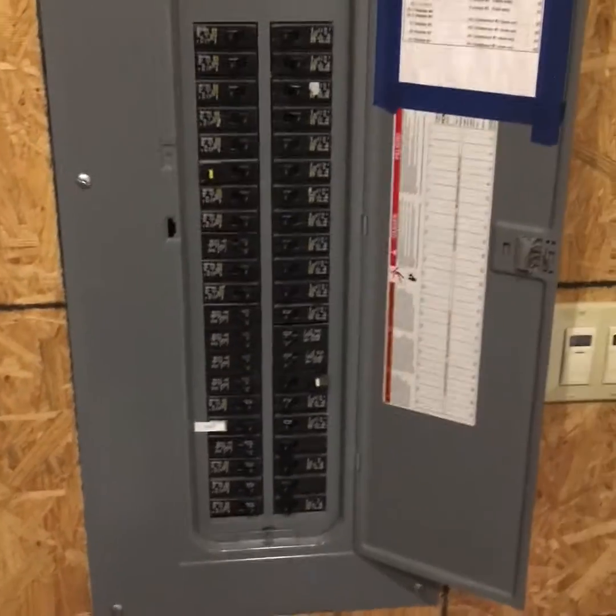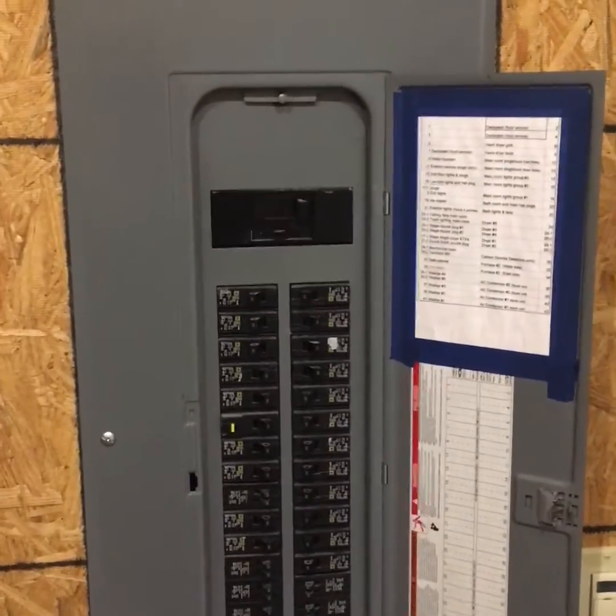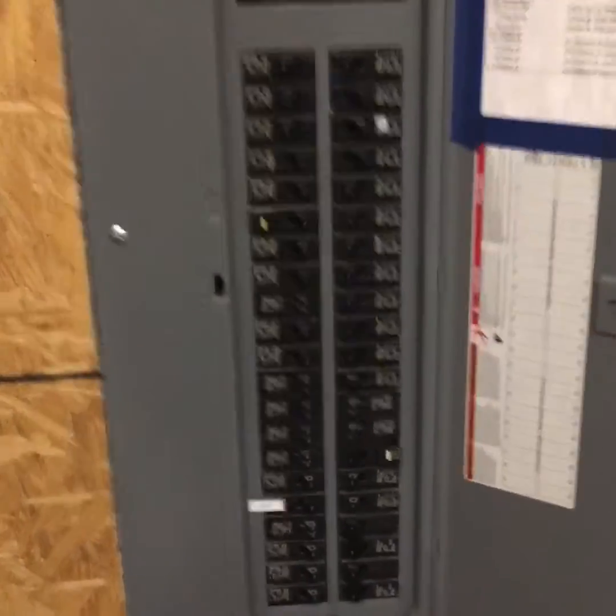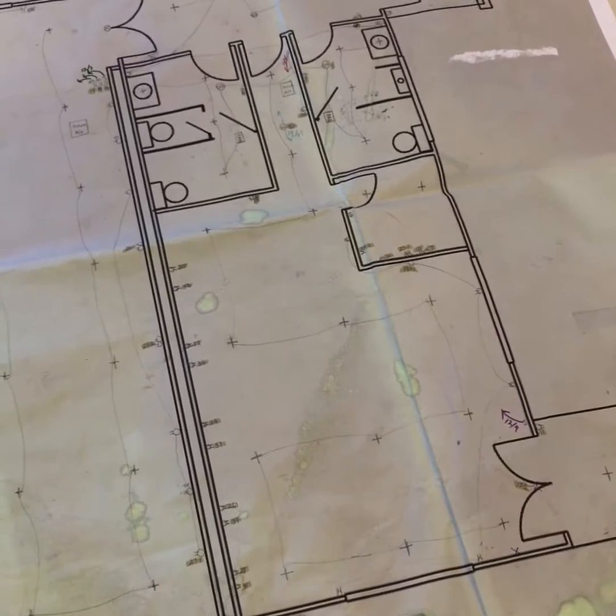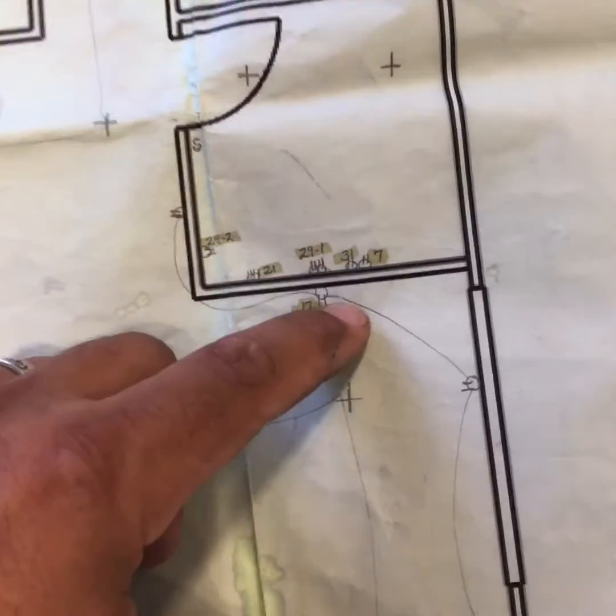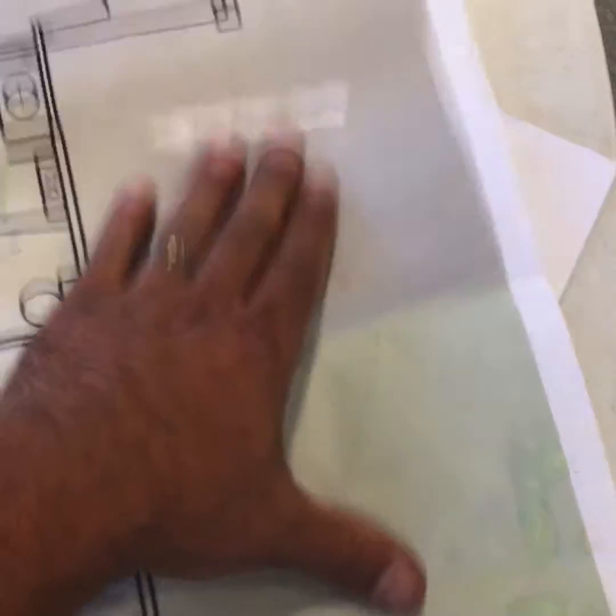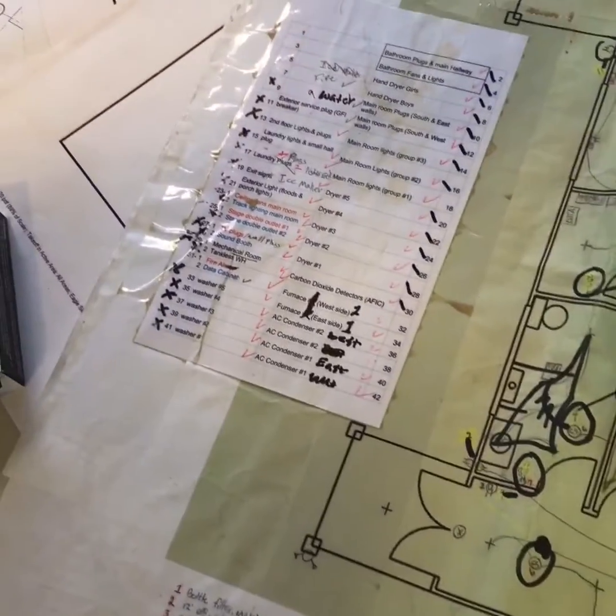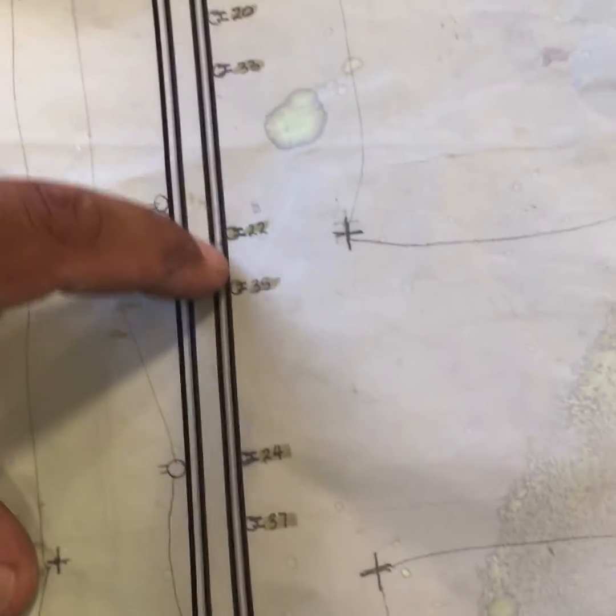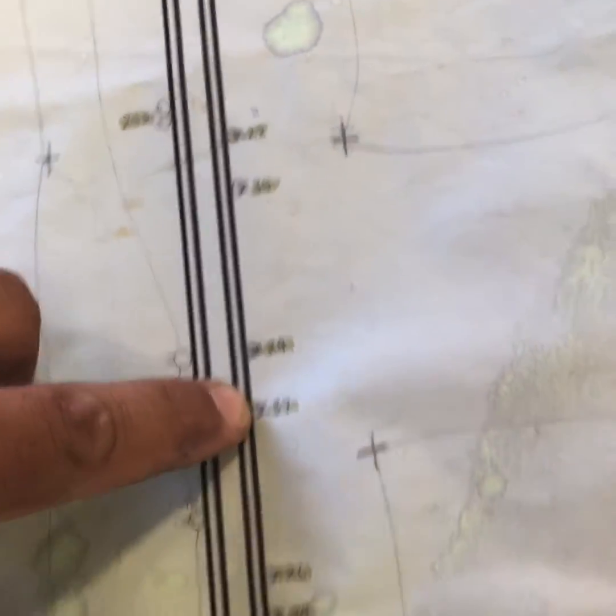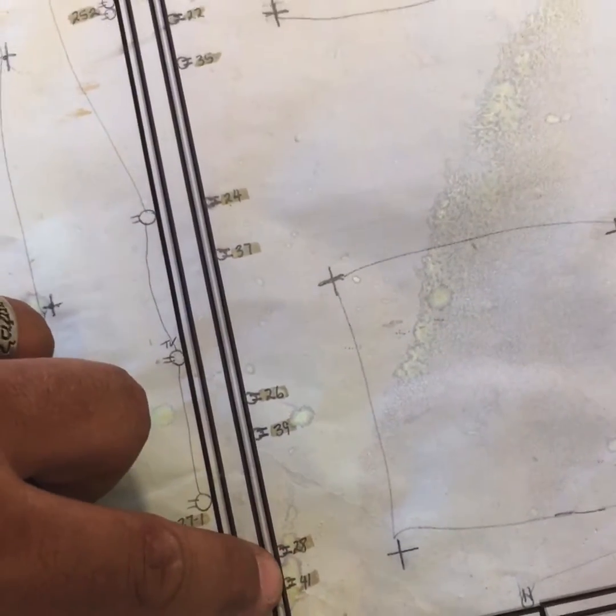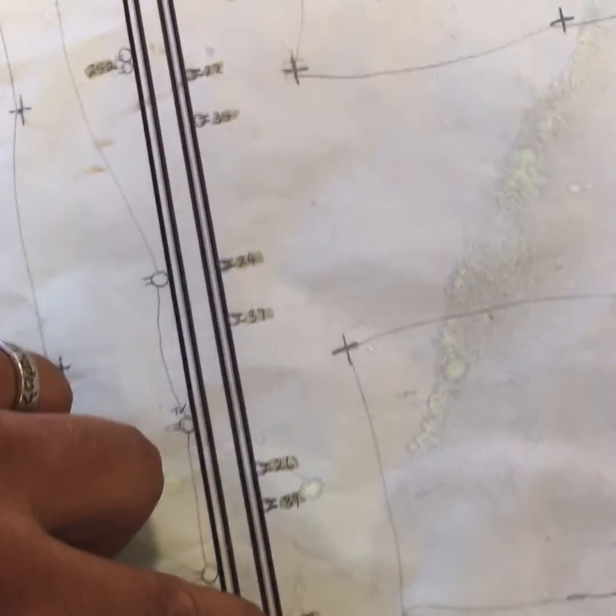And then I think I am going to go up and try to find the drawing that I did for this building and kind of show you what that looks like as well. So here's the electrical plan, the drawing for that building. Here's where the panel is, and we've got 20. I'm not sure what happened, but somebody pulled off the little breaker ledger. But essentially, we've got number 19. That's our water fountain. Here are our plugs, our washing machines and dryers here. We have a dedicated circuit for each of those. These dryers are 120 volt. They're gas dryers. I didn't have to do dedicated, but we did.